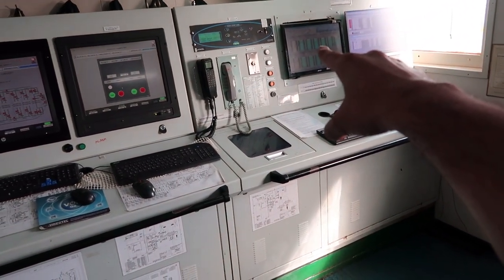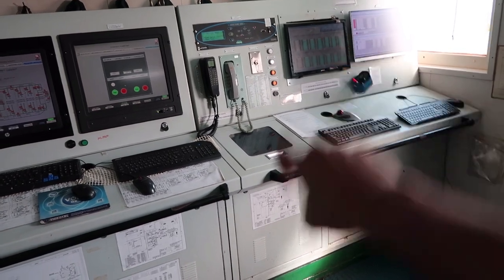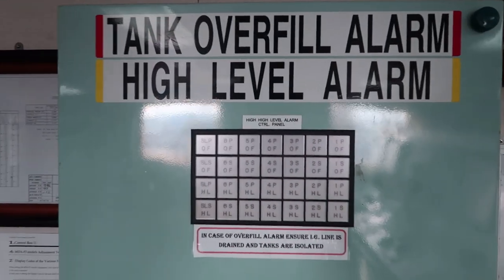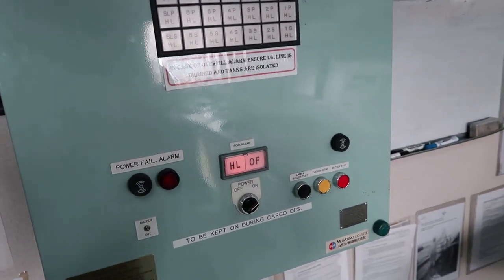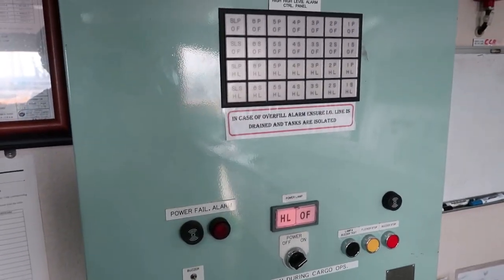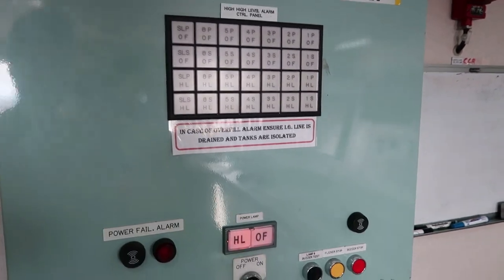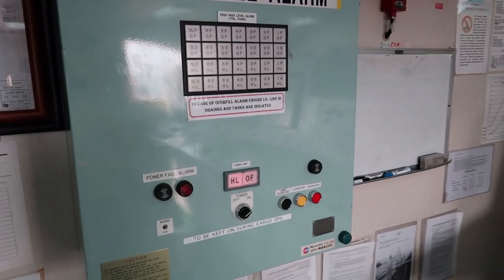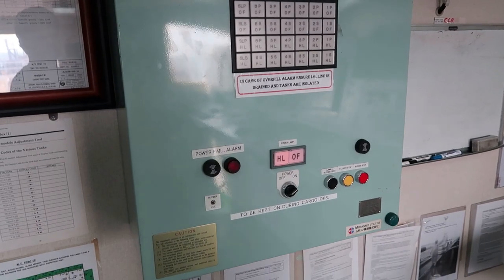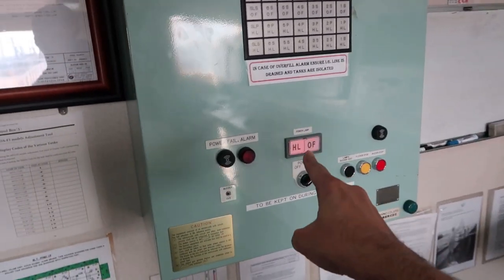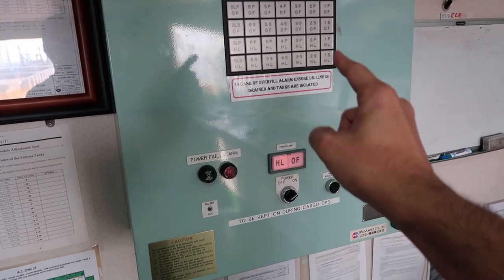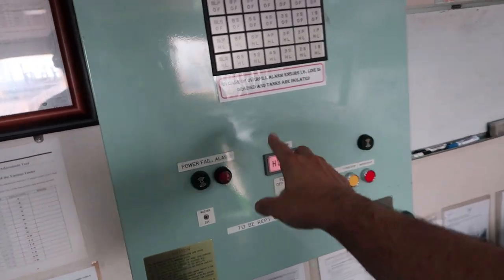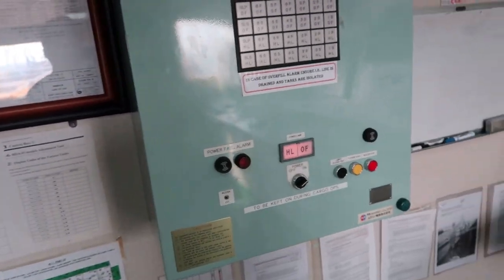And we get all those data on that computer together for all the tanks. Next we have tank overfill and high level alarms. These are independent systems. They give us alarms at 95% and 98% for all the cargo tanks. And this alarm rings loudly on deck as well as in CCR. Very important to keep this panel on before any loading or discharging operations because this is the one which is going to save you from overflowing any tanks.